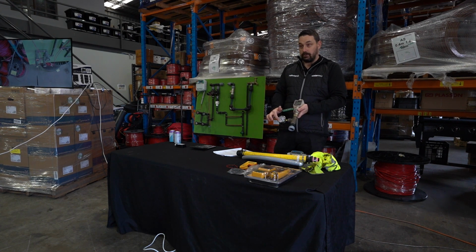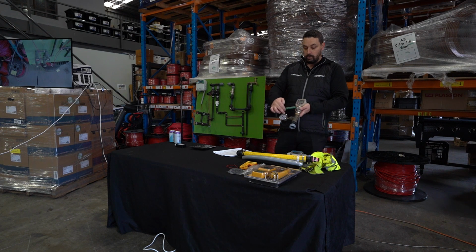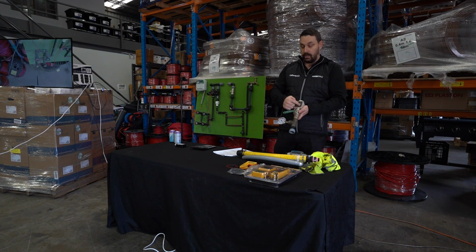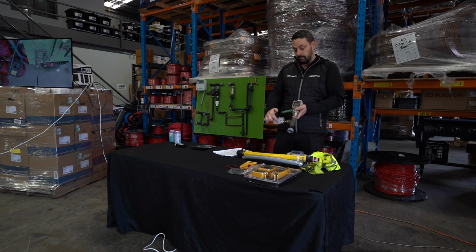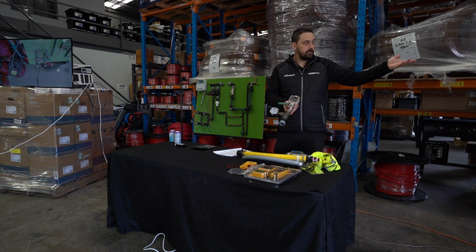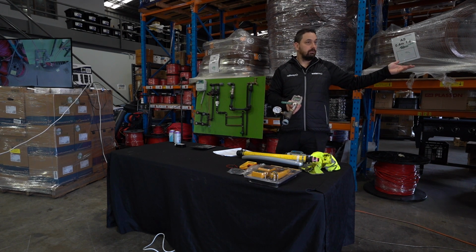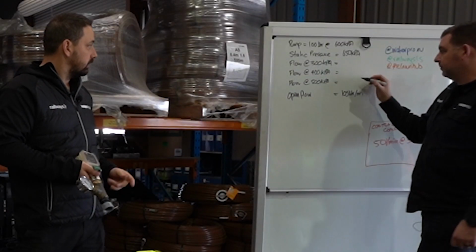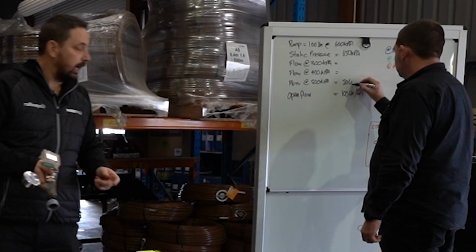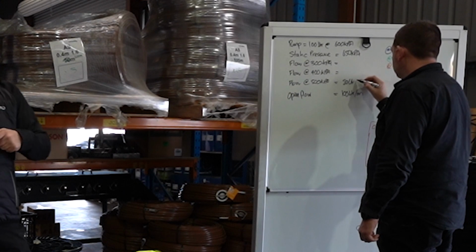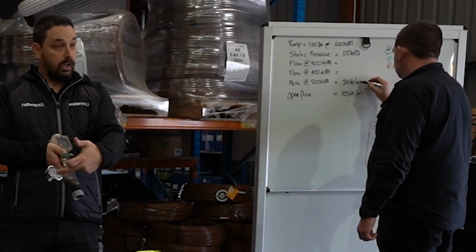And once we see 500 kPa on the dial, we then measure with this unit. It'll tell us a flow rate, obviously at 500 kPa, and then we would record that. So for this instance, we might say at 500 kPa, let's say 20 litres a minute.